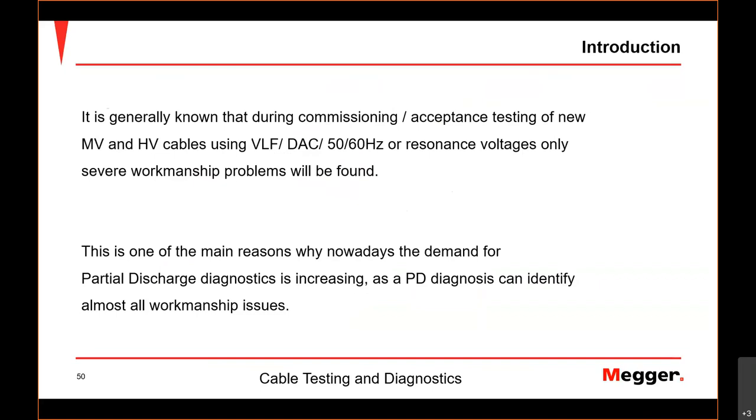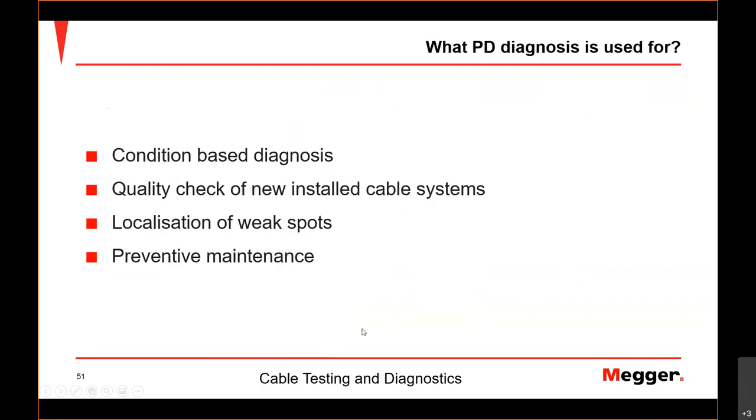And that's why partial discharge, PD, is the common method for workmanship problems. You could do that. It's a condition-based diagnosis. So you see the condition of the cable. It's not time-based, where you say my cable is 30 years old, I will exchange it. Whether it's good or bad, I don't know, I will just exchange it. Here you can diagnose the condition.